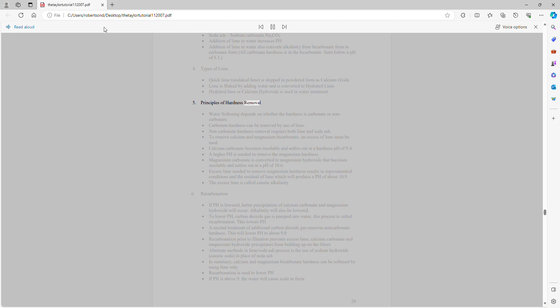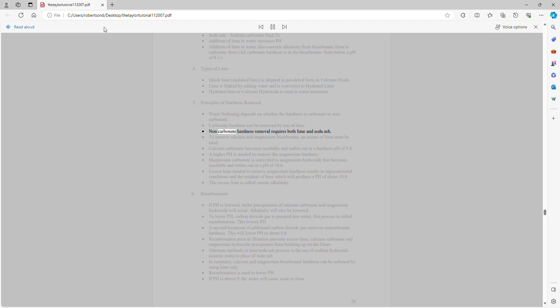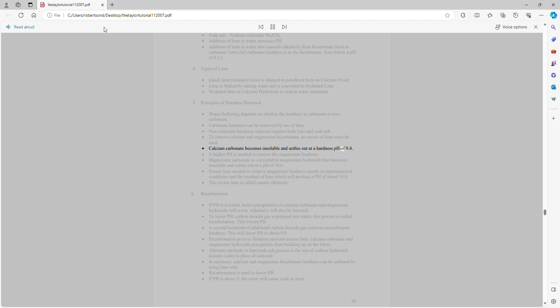Principles of hardness removal: Water softening depends on whether the hardness is carbonate or noncarbonate. Carbonate hardness can be removed by use of lime. Noncarbonate hardness removal requires both lime and soda ash. To remove calcium and magnesium bicarbonate, an excess of lime must be used. Calcium carbonate becomes insoluble and settles out at a hardness pH of 9.4. A higher pH is needed to remove the magnesium hardness.